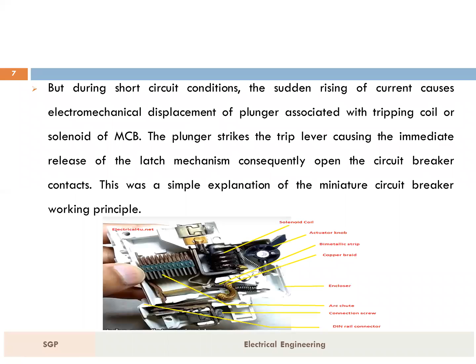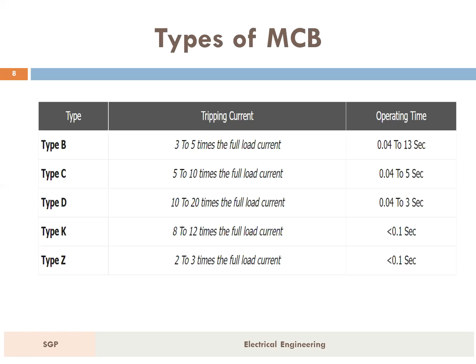Types of MCB. As we can see in the PPT, there are 5 types of MCB: Type B MCB, Type C MCB, Type D MCB, Type K MCB, and Type Z MCB. The operating time of Type B MCB is 0.04 to 13 seconds. The operating time of Type C MCB is 0.04 to 5 seconds. The operating time of Type D MCB is 0.04 to 3 seconds. And Type K and Type Z operate in less than 0.1 seconds.